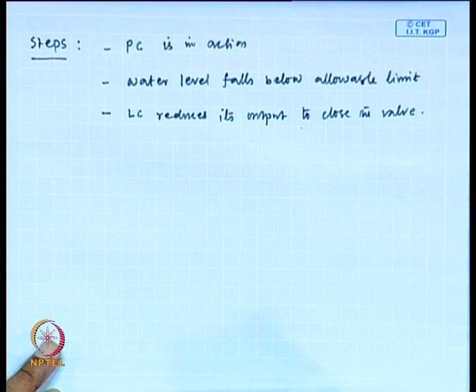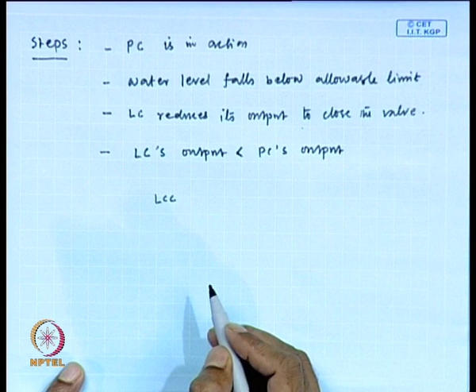Fine. Now, when the level controller's output drops below the pressure controller's output, the LSS selects the level controller's output signal. This is a very important point. If the level controller output falls below the pressure controller's output, then LSS selects the lower value. So, you see, previously the LSS selected the pressure controller output. Now, as the liquid level falls below the allowable limit, the level controller's output reduces, and when it falls below the pressure controller output, the LSS selects this lowest amount, I mean the level controller's output.